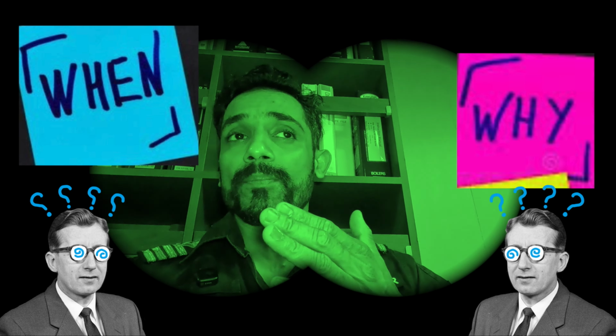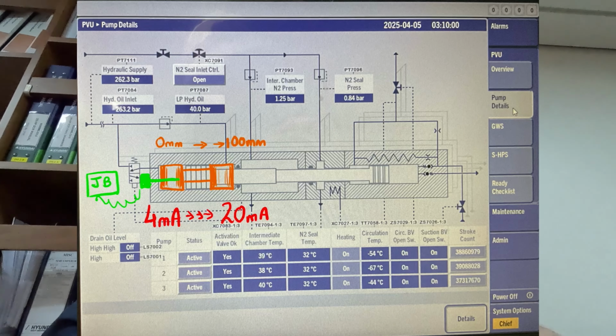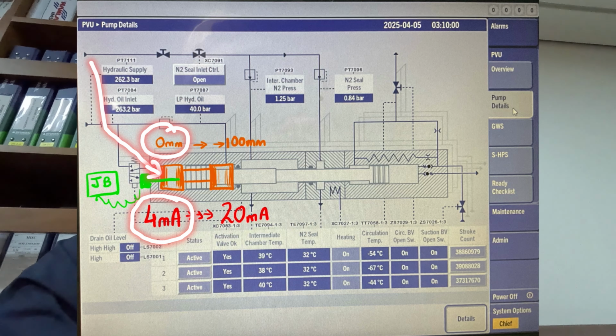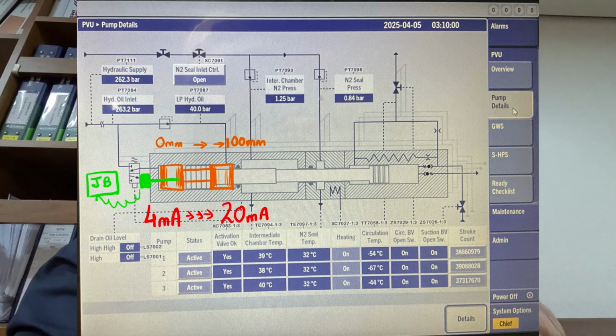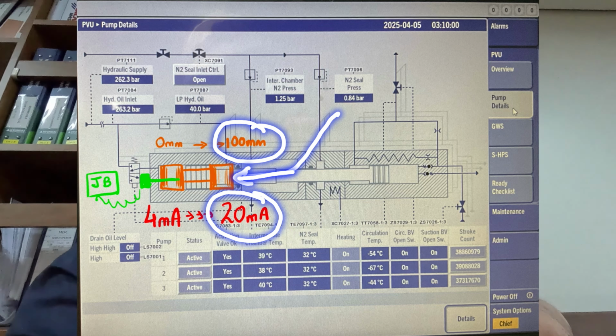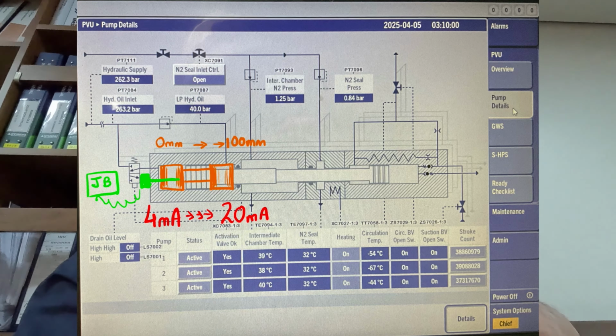So when do we do the calibration and why is it required? Well, the pump needs to know what the end position is and what the start is, what the end of the stroke is and what the start of the stroke is. The start of the stroke is 0 millimeters, at 4 to 4.5 milliamps of current, and the full stroke, 100 millimeters, is at between 19 and 20 milliamps, because it works on a simple 4 to 20 milliamp current, calibrated from 0 millimeter stroke at 4 milliamps to 100% stroke, in this case 100 millimeters, at 20 milliamps. It's very important that the pumps are calibrated so that they perform well and are in sync with the other pumps, usually 3.